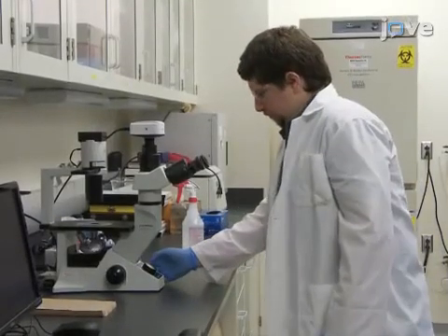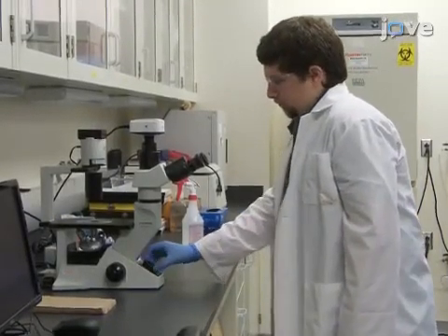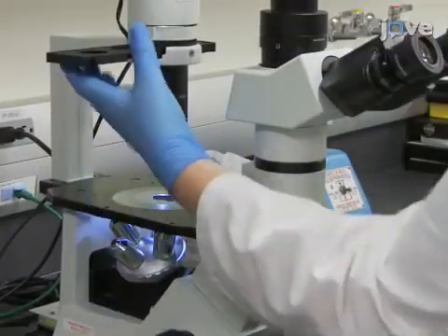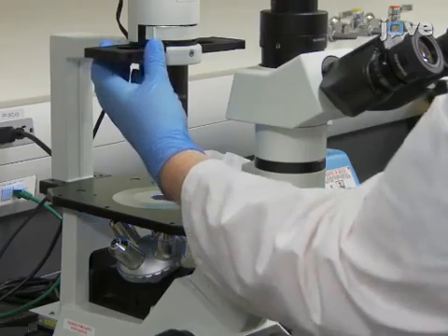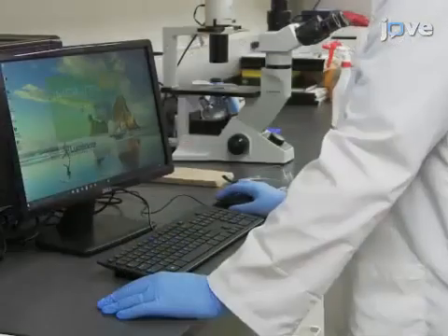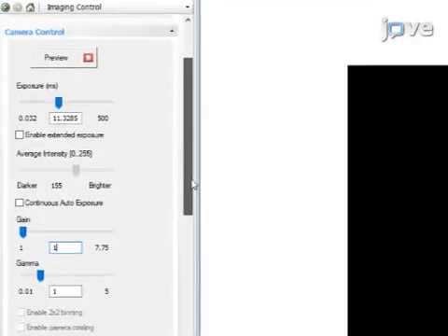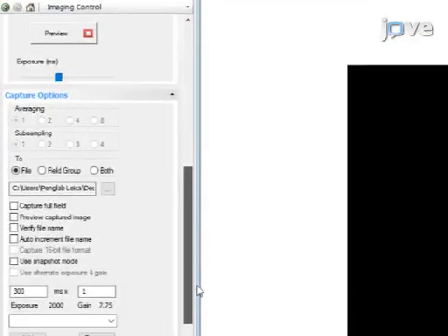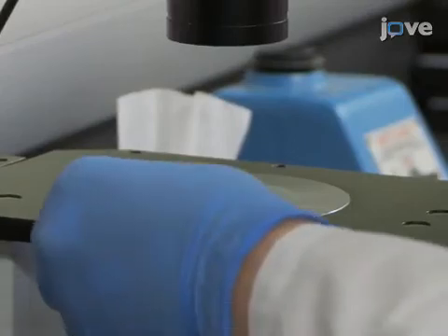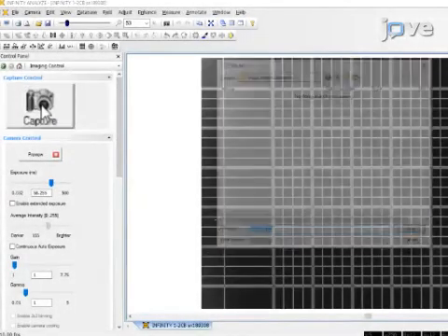To begin, set the microscope illumination to maximum, switch to the 4x objective, and ensure that the phase contrast filters are in use. Then, within the microscope software, set the image capture settings to their default values. Now place a standard hemocytometer onto the microscope stage and capture an image for the image volume calibration step. Adjust the exposure time as needed.